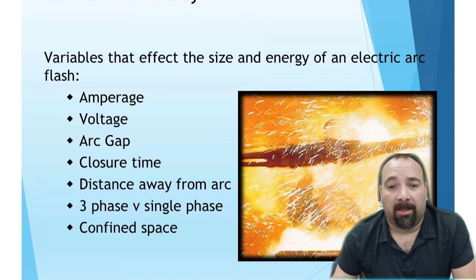There are many variables that affect the size and energy of an arc flash: amperage, voltage, the actual gap that the arc is jumping, that the electricity is jumping from one side to the other. Remember, electricity is always looking for the closest path to ground, so that's what it's trying to find. The time it takes to jump has an effect on it. The distance away from the arc, is it single phase, are we talking three phase, and are we in a confined little space, or a big open electric room, or did you just open the closet door and there's the panel? So those are all factors and variables that come into the size of the arc flash and how much energy it actually puts out.